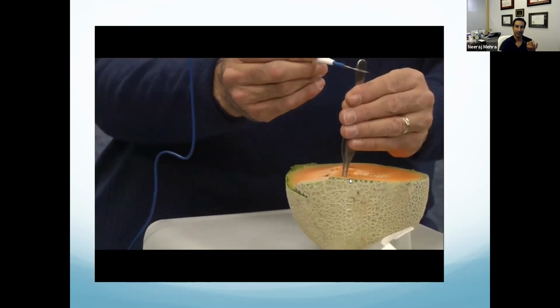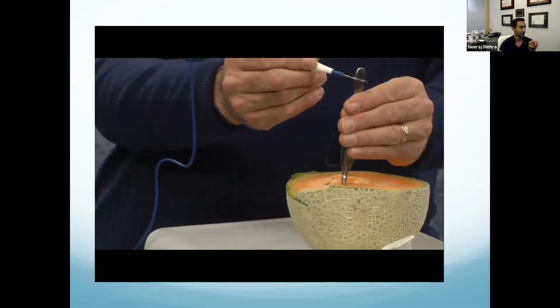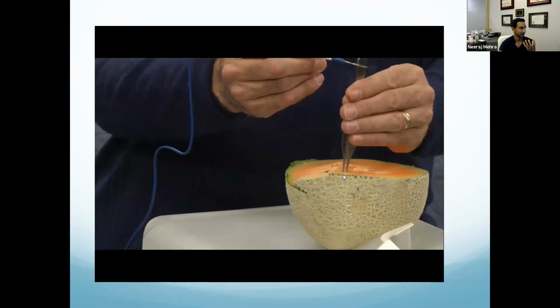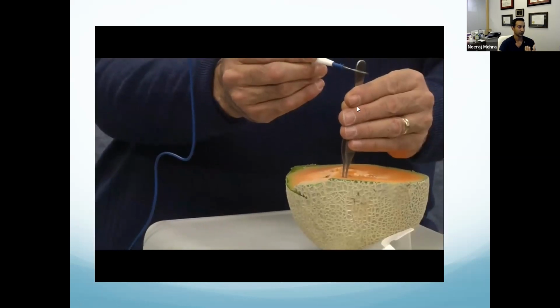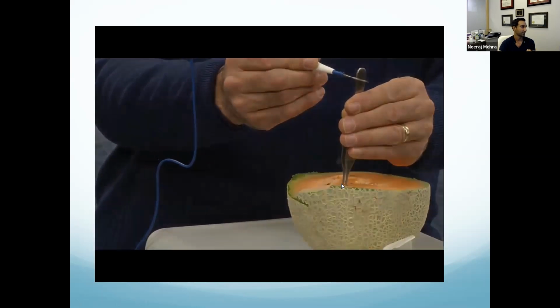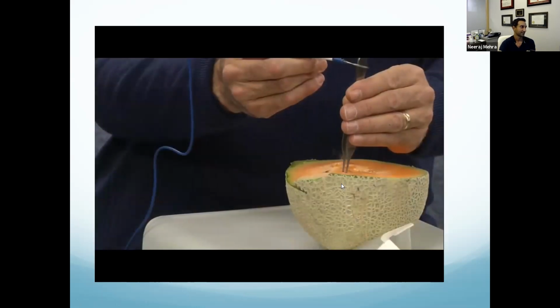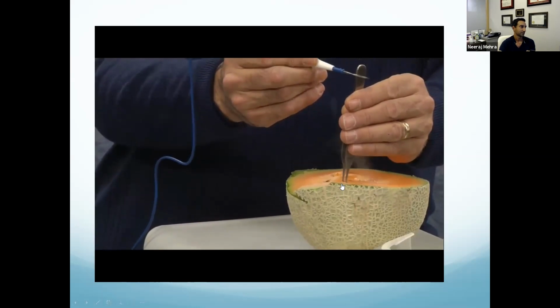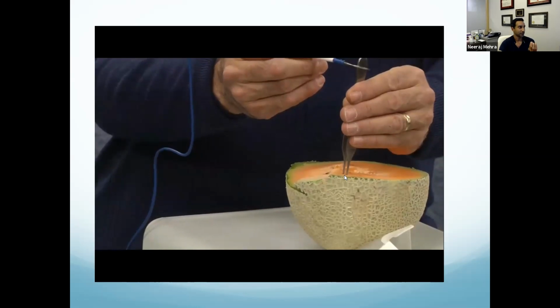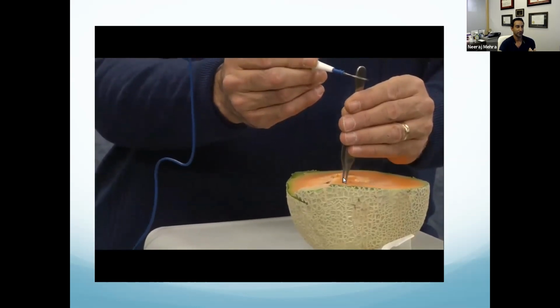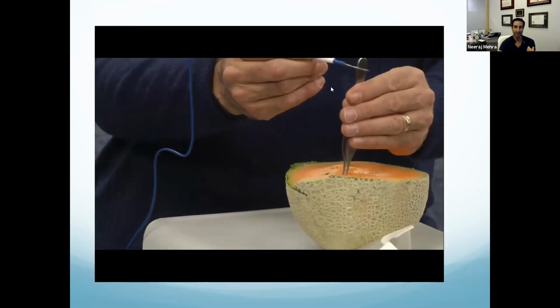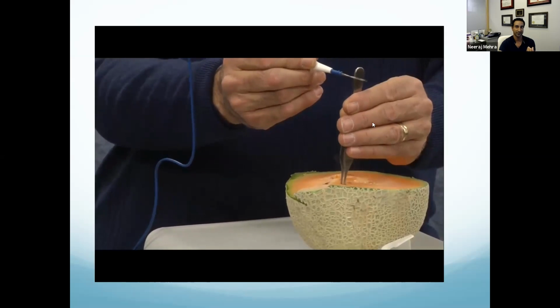So cut has two benefits. One is it's low voltage. It's the high voltage, the sudden jump, that gives you that zap, so you want low voltage. And also, what are you trying to do when you do this? We're trying to stop something bleeding, right? As I said, you want low and slow over time. So the cut mode creates safety by giving you a low voltage, so you're less likely to get zapped, and it also provides low energy over time, so you're more likely to stop that bleeding vessel.